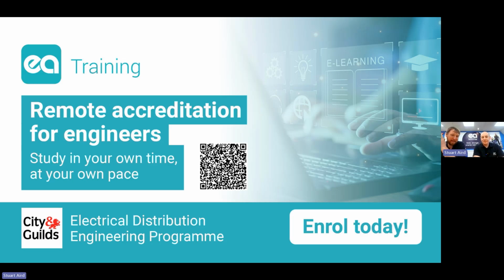No PD is ideal. I would probably say internal PD tends to progress slower, and once you've found surface activity, it will progress reasonably quickly, especially if things like high humidity are present. So in terms of time to failure, you're probably going to get more warning off an internal source than off an external one, but it's a very general comment. In terms of what you can do more about, quite often it's the opposite way around. If you find external or surface activity, things like controlling the environment, separating cores, moving the stress away—there are quite often really simple interventions you can do for surface, or external, activity which are cheap and easy to do and will make a big difference to the lifespan of the gear. That is harder on the internal side; internal, you're heading towards component replacement.